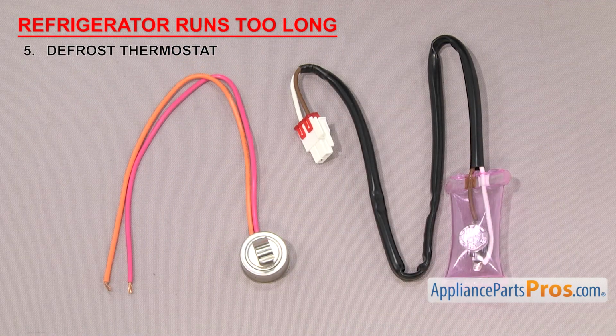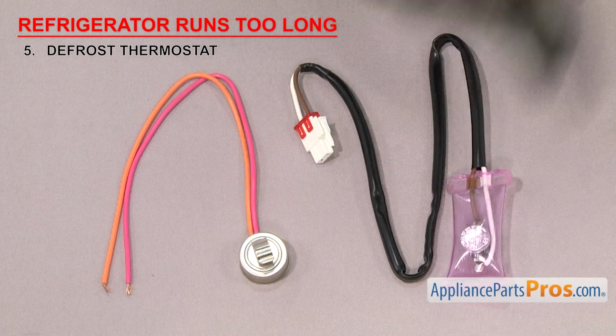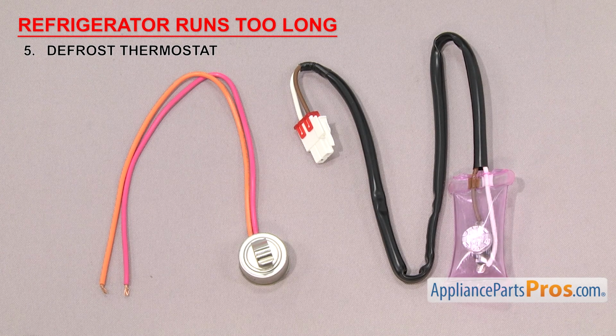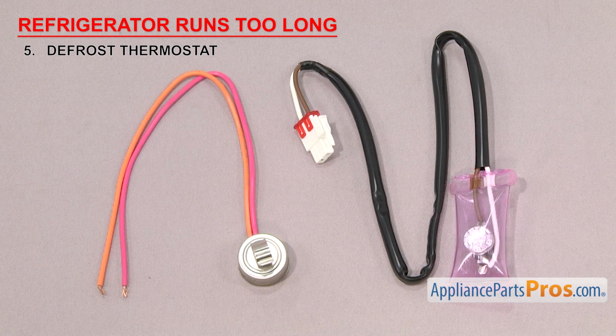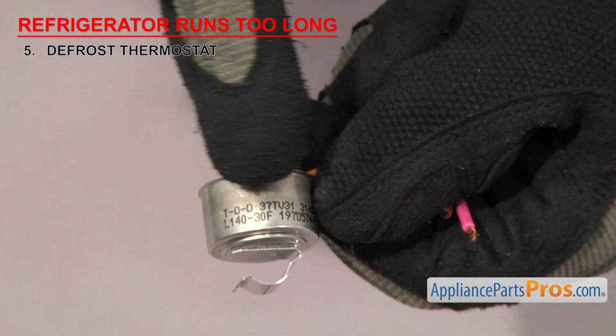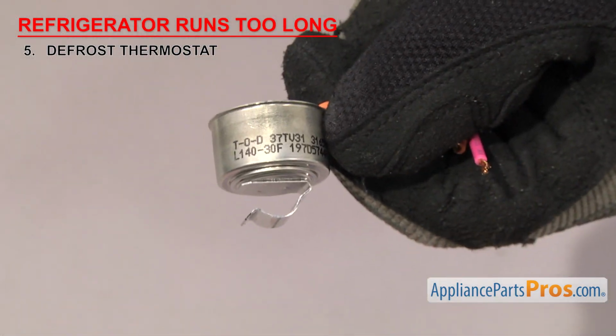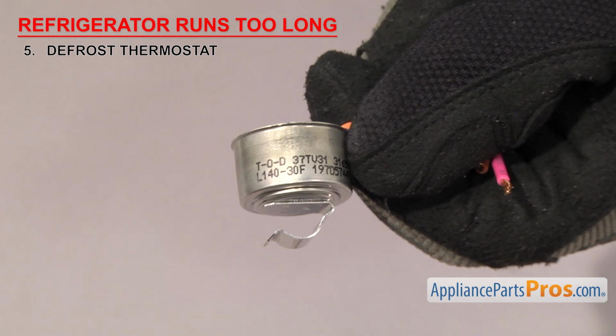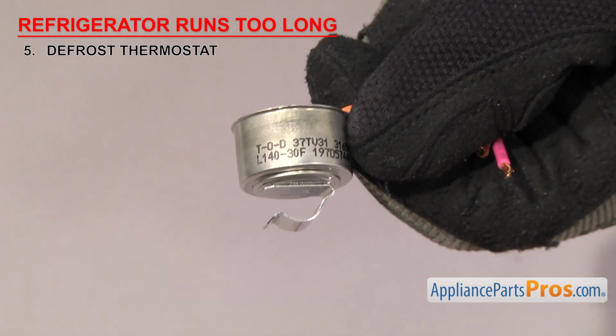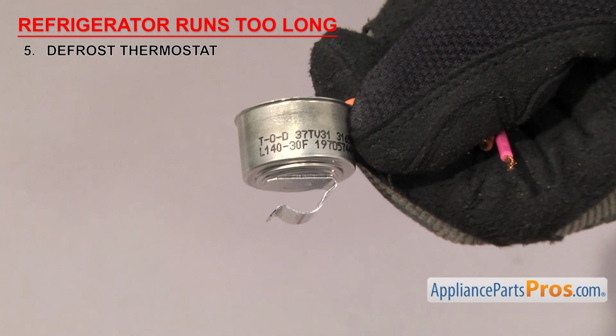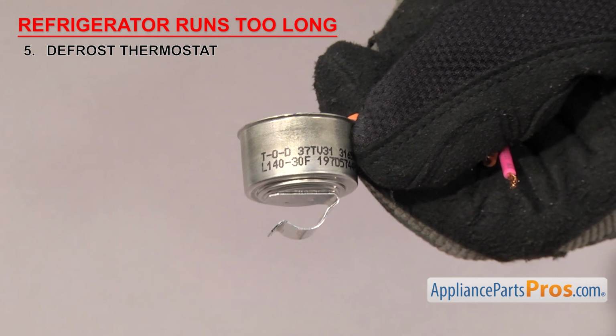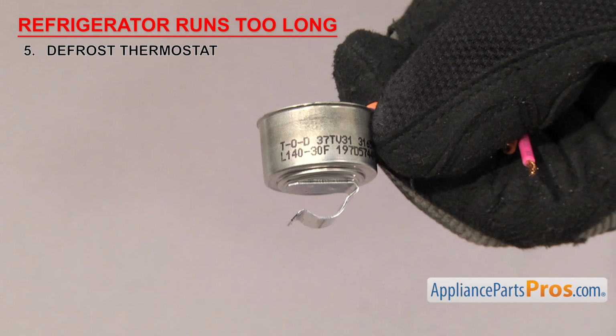Now we need to check the defrost thermostat. It's a safety device that shuts off the defrost cycle if the freezer gets too warm. Defrost thermostats cut the power off to the heater if the temperature gets too hot. This is so it doesn't get too hot in the freezer section and start melting the frozen food. They usually have a temperature rating stamped on them to tell you what temperature they turn the power off to the heater. Depending upon the manufacturer, it could be either in Fahrenheit or Celsius. Sometimes they're marked with a C or an F, and sometimes they're not. They vary in temperature, so check your thermostat to see what it's rated at.